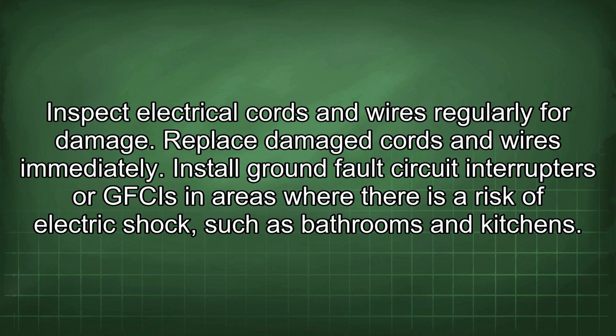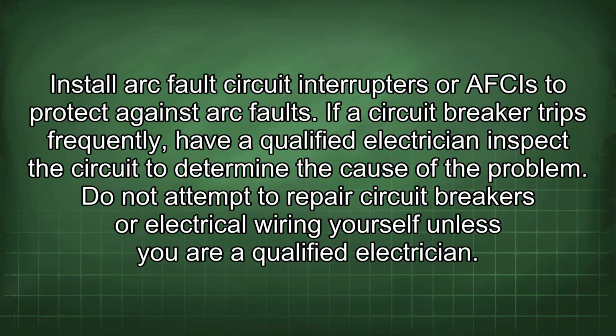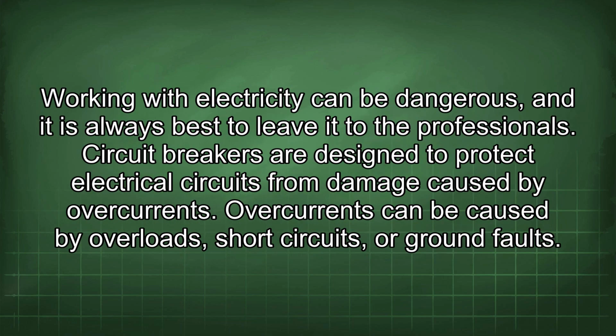Install ground fault circuit interrupters, or GFCIs, in areas where there is a risk of electric shock, such as bathrooms and kitchens. Install arc fault circuit interrupters, or AFCIs, to protect against arc faults. If a circuit breaker trips frequently, have a qualified electrician inspect the circuit to determine the cause of the problem. Do not attempt to repair circuit breakers or electrical wiring yourself unless you are a qualified electrician. Working with electricity can be dangerous, and it is always best to leave it to the professionals.